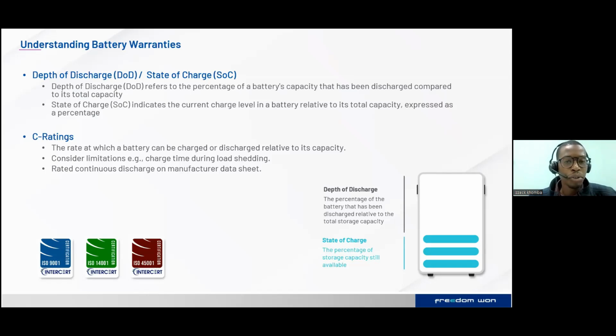Then your state of charge, which is normally abbreviated SOC, indicates the current charge level in the battery relative to its total capacity, and is expressed as a percentage. So those are terminologies we need to be familiar with. Normally, they appear on the warranty documents. The C rating as well is the rate at which a battery can be charged or discharged relative to its capacity. So we need to consider limitations which are stipulated on the manufacturer data sheet and the warranty document, which translate to the charge time during load shedding that we need to consider when looking at the C rating. So when speccing your system, you need to look at the average continuous discharge of your load and ensure that it's within the battery C rating.